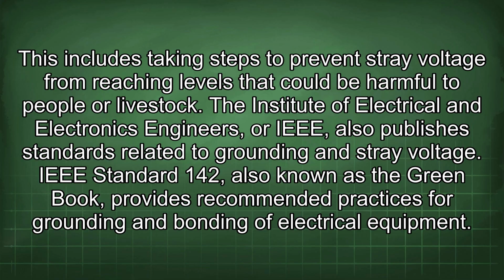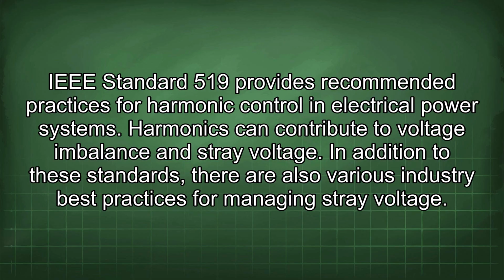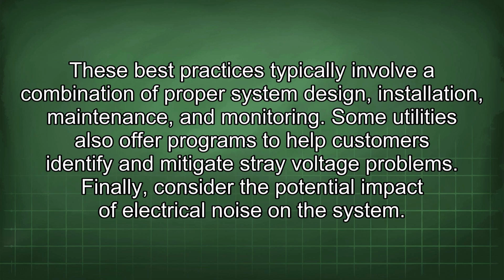voltage. IEEE Standard 142, also known as the Green Book, provides recommended practices for grounding and bonding of electrical equipment. IEEE Standard 519 provides recommended practices for harmonic control in electrical power systems. Harmonics can contribute to voltage imbalance and stray voltage. In addition to these standards, there are also various industry best practices for managing stray voltage. These best practices typically involve a combination of proper system design, installation, maintenance, and monitoring. Some utilities also offer programs to help customers identify and mitigate stray voltage problems.